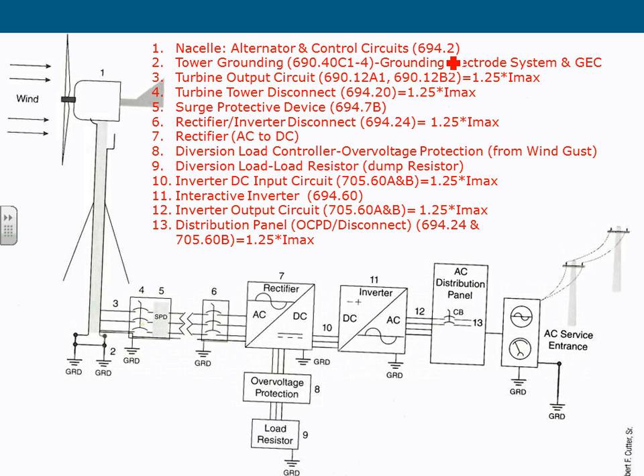They call it I maximum. The I maximum is defined in the code as the maximum current that this unit will generate at a speed of 25 miles per hour. That's the speed they use to generate the maximum current. Okay, so we have the conductors land into a disconnect for safety.